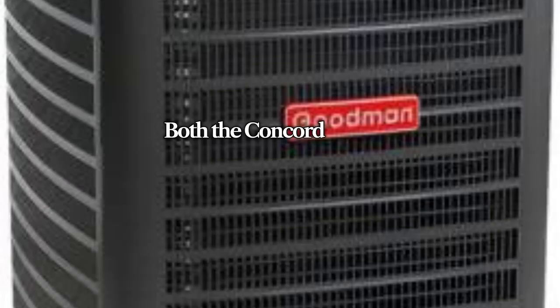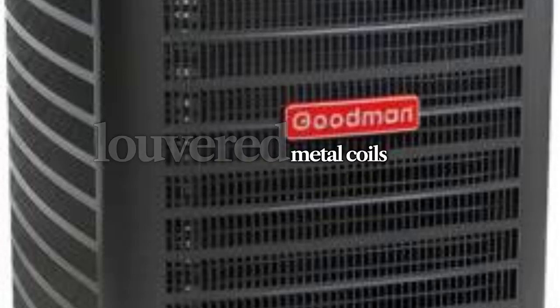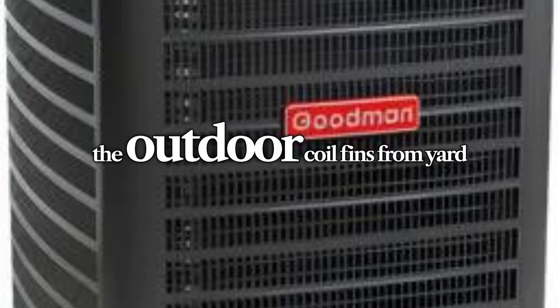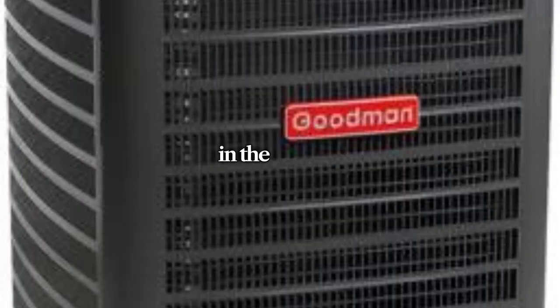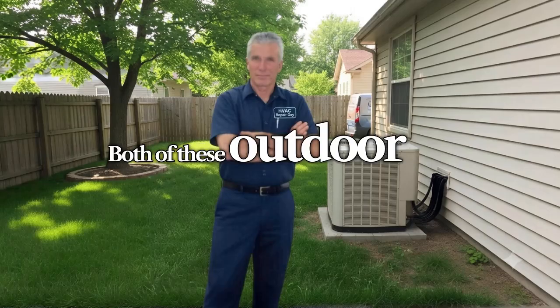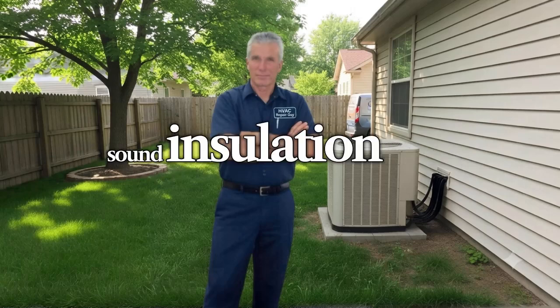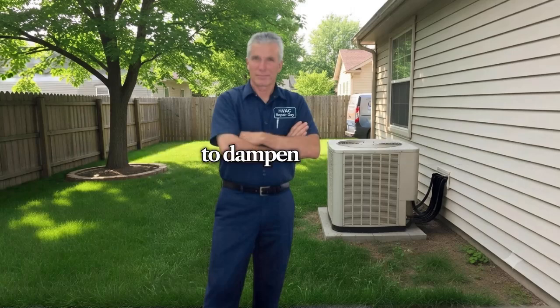When you step up to both of these units, you are looking at top-tier cabinet construction. Both the Concord and the Goodman use louvered metal coils to shield the outdoor coil fins from yard debris, hail, and stray rocks. Concord builds their cabinet right here in the USA. Goodman assembles theirs in the USA as well. Both of these outdoor units come equipped with a factory sound insulation blanket wrapped around the compressor to dampen mechanical noise.